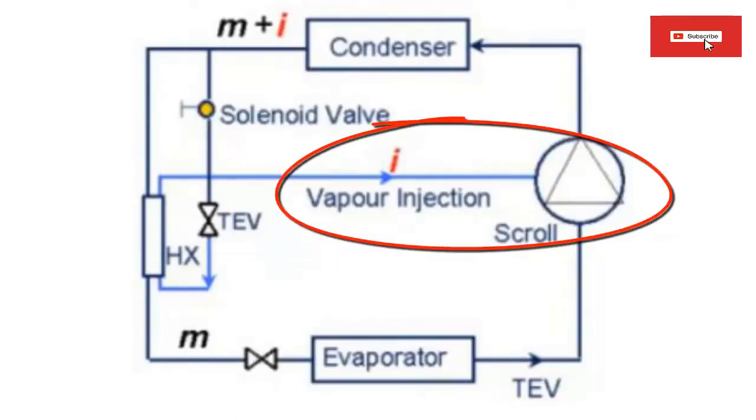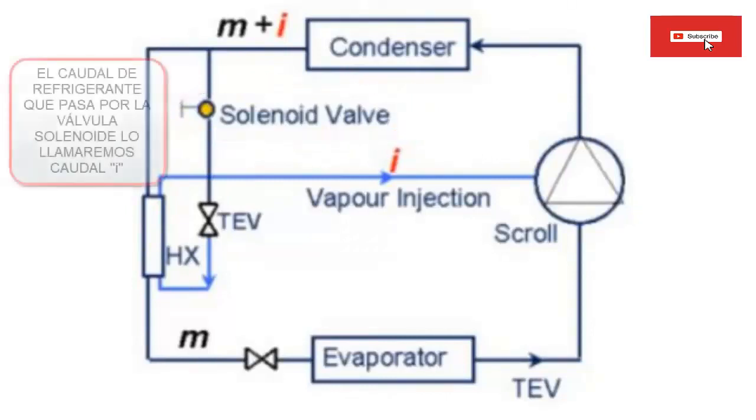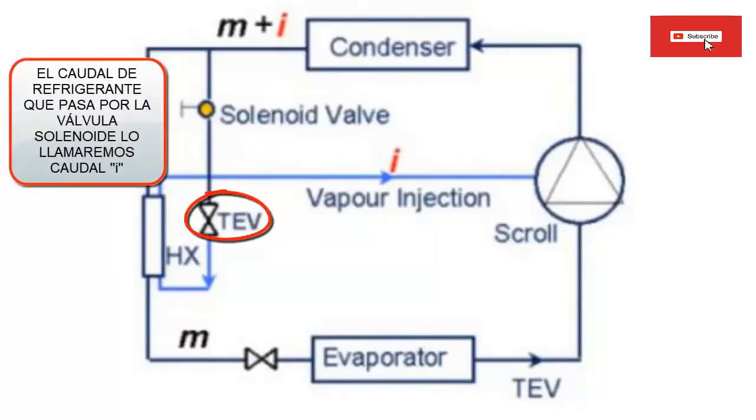3. In the economizer system, a solenoid valve is used to activate the passage of refrigerant at the condenser outlet with a flow that we will call I. 4. After the solenoid, an expansion valve is responsible for dosing and lowering the pressure of the refrigerant flow I.